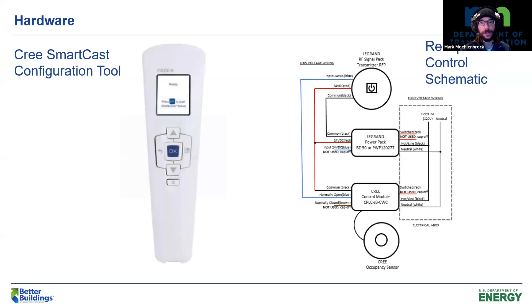On the right is a control schematic that shows specifically how the plug load was integrated with the lighting zones. On the bottom, it says occupancy sensor. That could be grouped with the other occupancy sensors that were integral to the luminaires and included in the occupancy zones. And it would communicate via a relay in the control module to the LeGrand signal pack transmitter, which communicated wirelessly to the plug loads, to the receptacles.